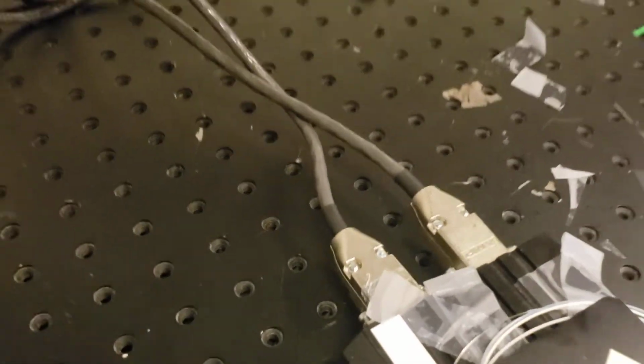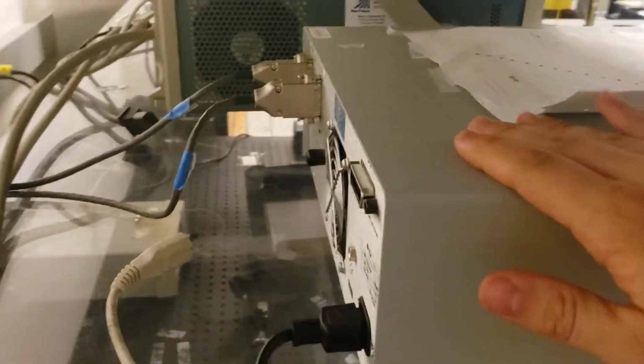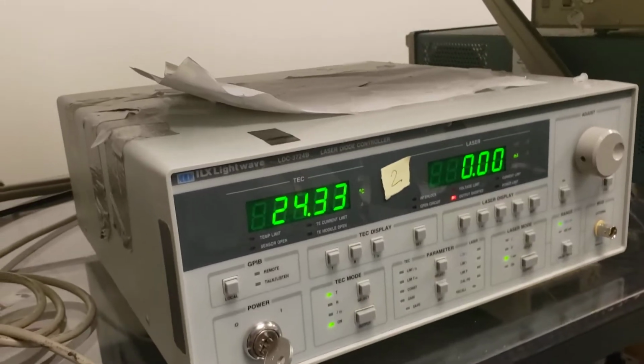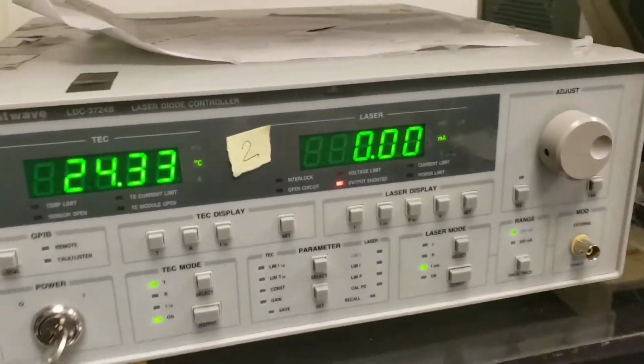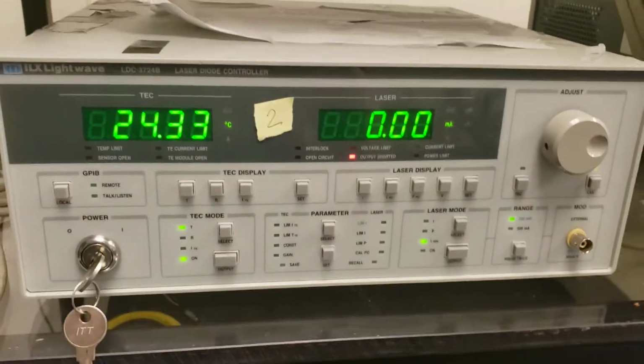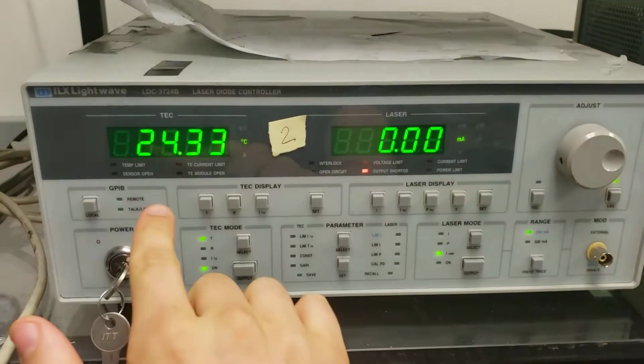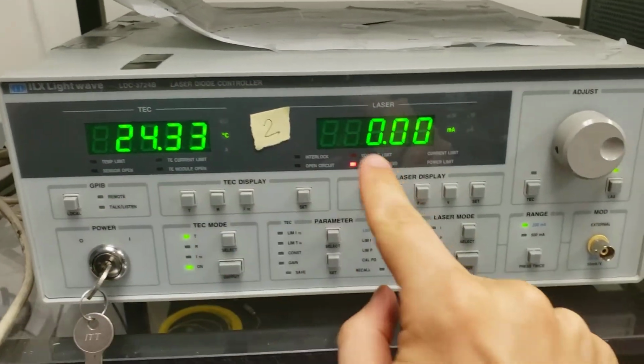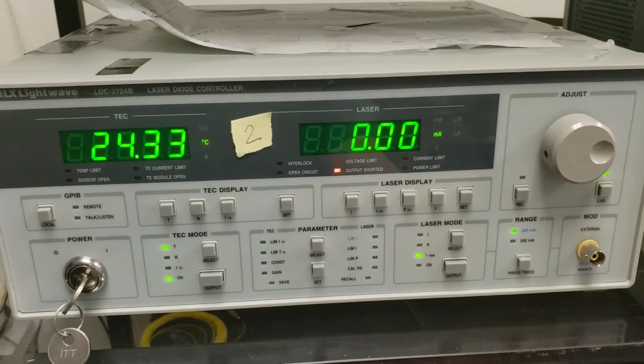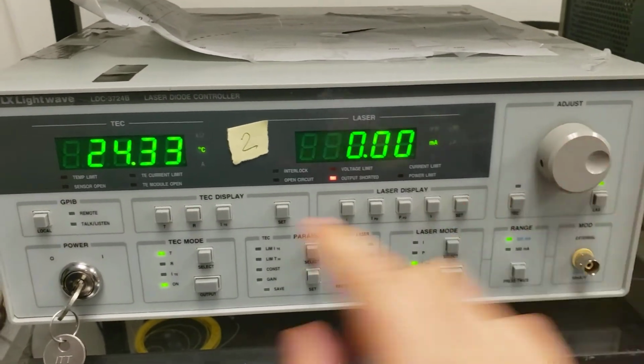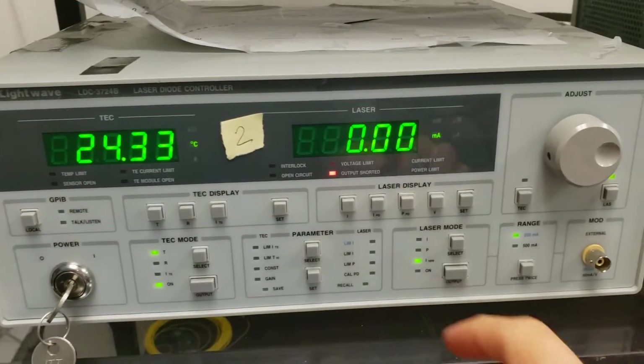Now the block itself has these two cables plugged into it, and these are attached to this device up here in the back, as you can see. Now this device here is a laser diode controller. Essentially it does two things. It both stabilizes the temperature of the cavity and also supplies it with electrical current. And you can use this knob here to adjust both those factors. How hot do you want the cavity to be and how much current do you want to supply it?